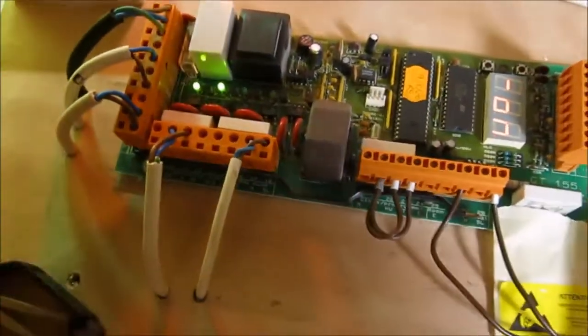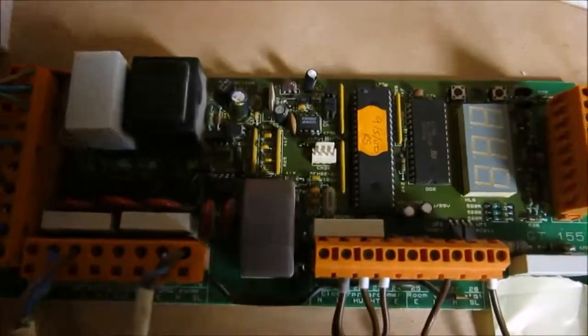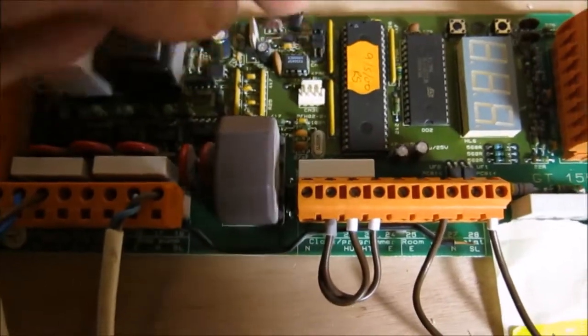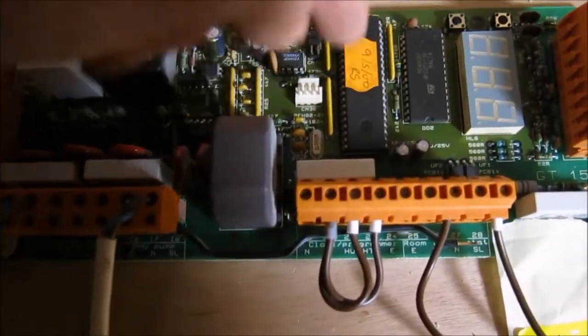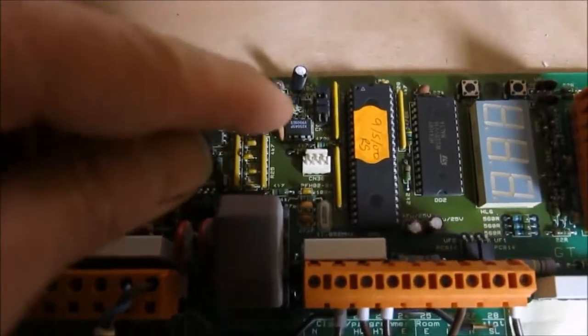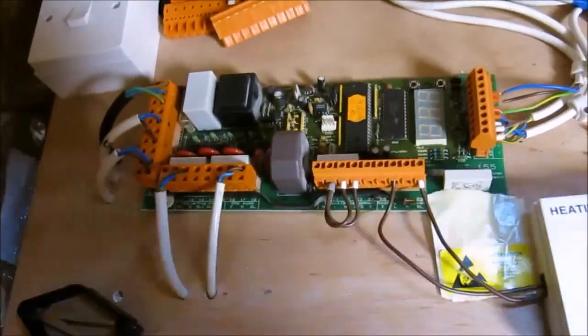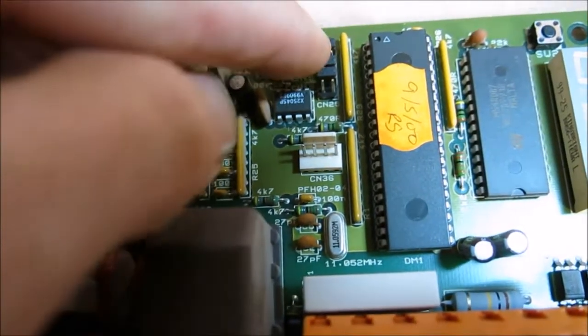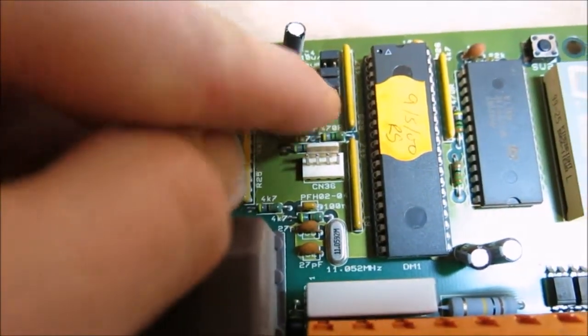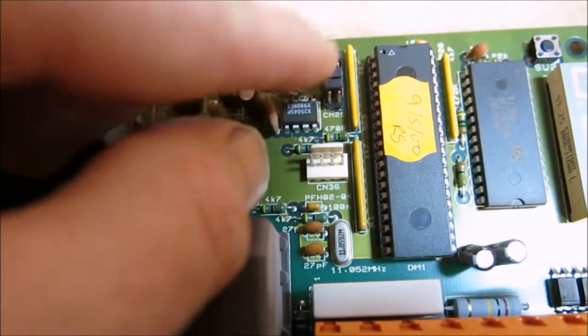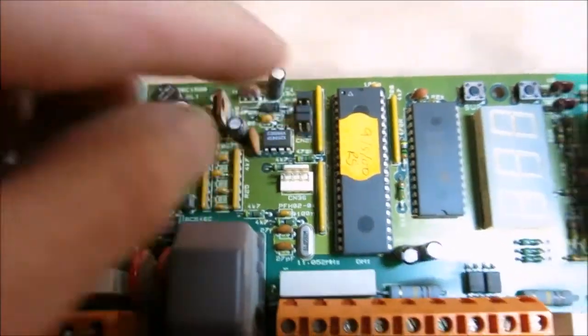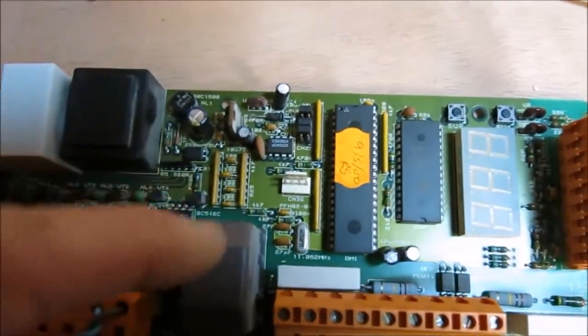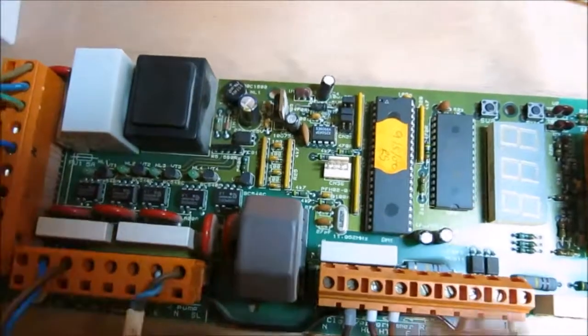Now there is a self-test facility on these, and this is an older firmware board. The latest one is version 29, used as a white label. On the version 29, if I just flick this light on - you have to move one of these jumpers here onto position 5. This is configured for Boilermate 2000, by the way. You move it onto position 5, turn the unit off, move it, then turn it back on, and it will cycle through the self-test.